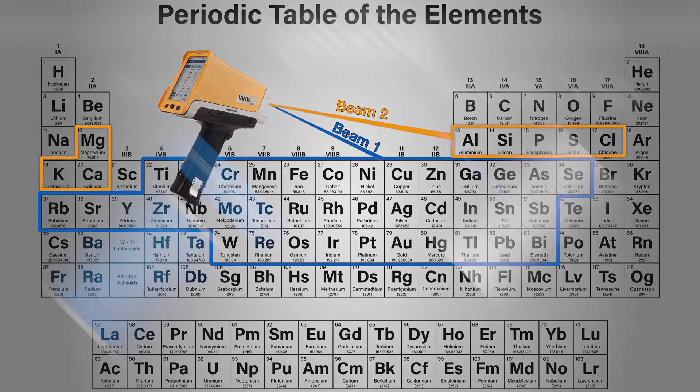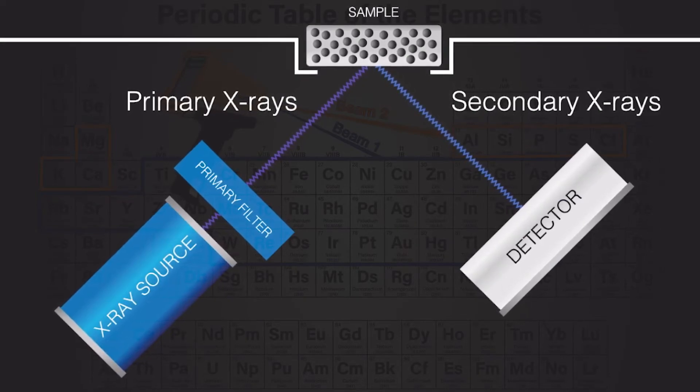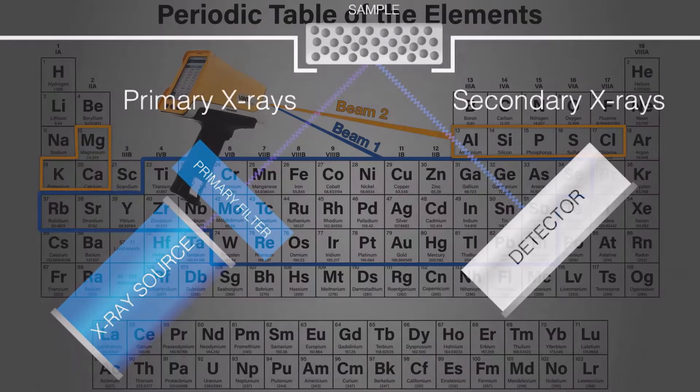and some filtration that we position in front of the X-ray. With these three things, we can optimise the analyser for different elements and our systems utilise options of one beam modes, two beam modes or three beam modes.